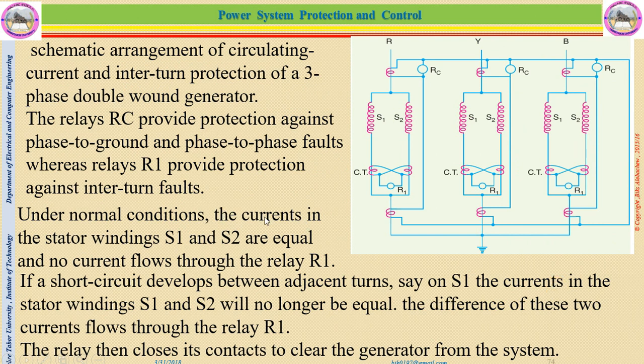So under normal conditions, the currents in the stator windings S1 and S2 are equal, and no current flows through the relay R1. If a short circuit develops between adjacent turns, say on S1, if an interturn fault happens, the currents in the stator windings S1 and S2 will no longer be equal. So the difference of the two currents may flow through the relay R1. Because if the two are equal, there is no current which passes across R1. But if the currents in S1 and S2 are not equal, there is a differential current. This differential current will pass through R1. So the relay then closes its contact to clear the generator from the system.